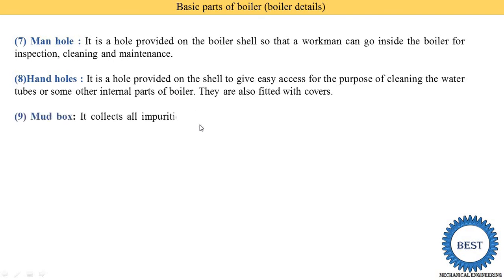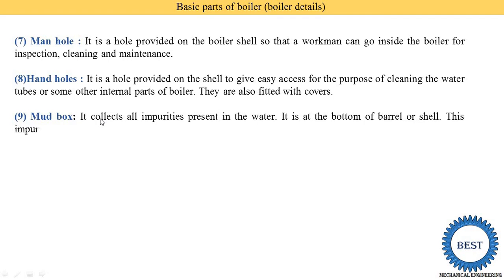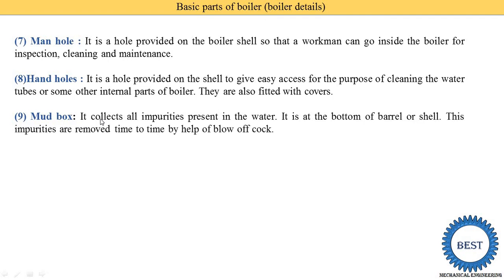The next part is the mud box. The mud box collects all the impurities present in the water. It is located at the bottom of the barrel or shell, and these impurities are removed from time to time by the help of a blowdown valve. Similar to how impurities settle at the bottom of a water tank, in fire tube boilers — where water is outside the tube — impurities settle at the bottom of the boiler shell and are removed using the mud box.